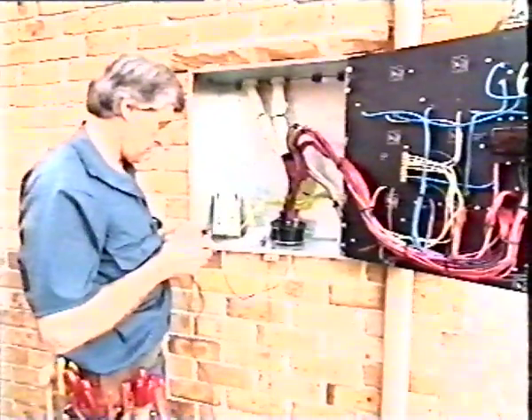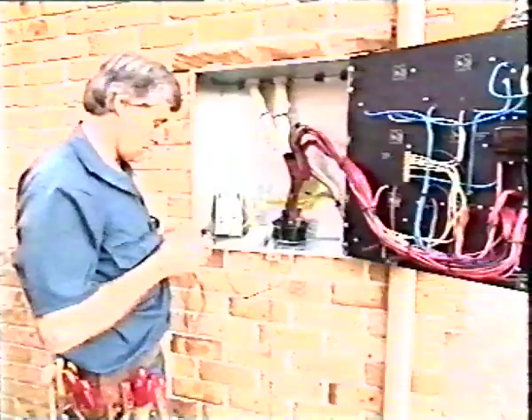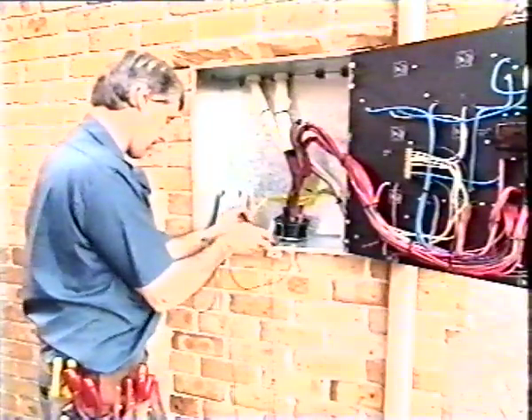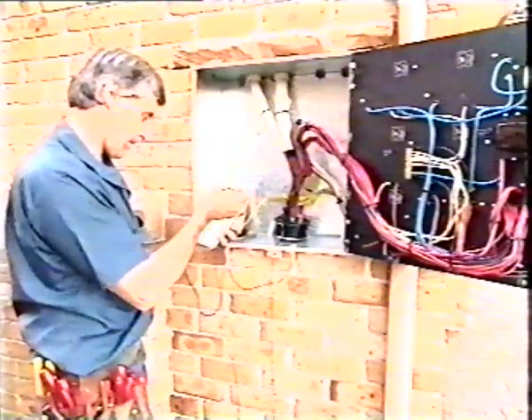Connect a short lead with a probe to the ohm meter. Connect the probe to the end of the trailing lead to measure lead resistance. This resistance must be deducted from the resistance values obtained during the earthing resistance tests.